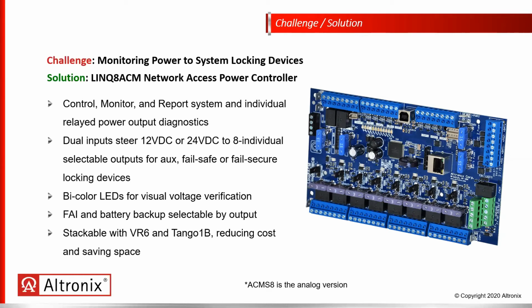So this product is a best practice from an installation perspective in the field, in that we don't have to run voltage through the relays on our door controllers. We can simply take a trigger input from the door relay on the access control panel. So a good card read fires the relay on the door controller. We take that trigger in, and then we control all the power to the locks out. And the benefit there is we're not introducing voltage directly to an access control panel, which may have onboard relays.